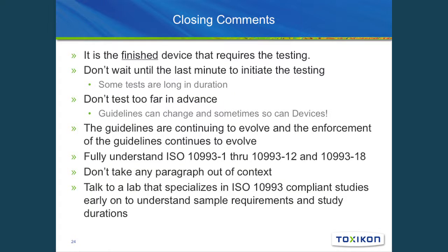Certainly, some biocompatibility and that class 6 testing I mentioned earlier is very useful in material selection, evaluating as you're going through your product development process whether or not you're incorporating or inducing anything that could have an adverse reaction. Very helpful there, but for the full range of biocompatibility testing, wait till you've gotten to your design freeze. You know that this is your device moving forward and your manufacturing process.